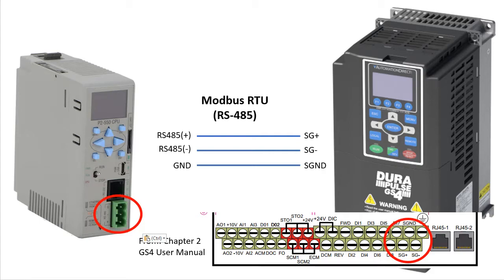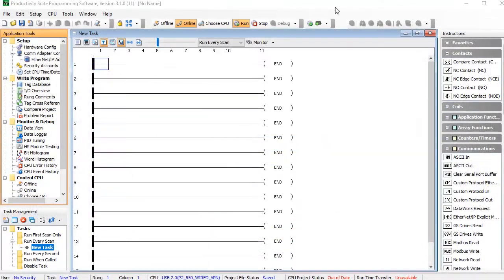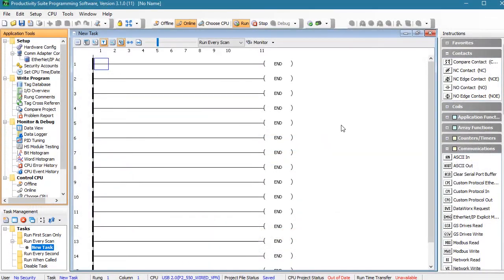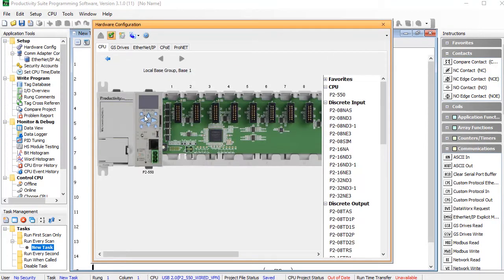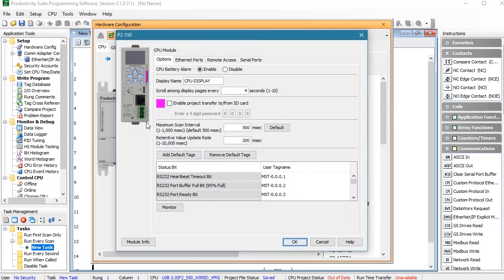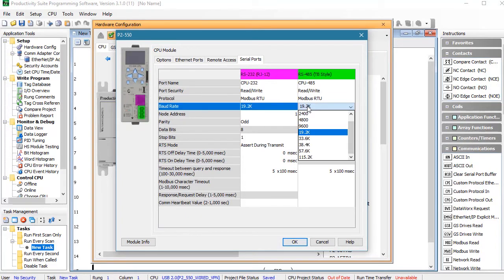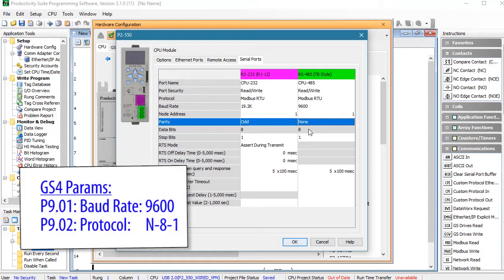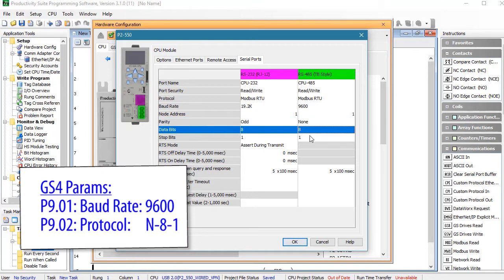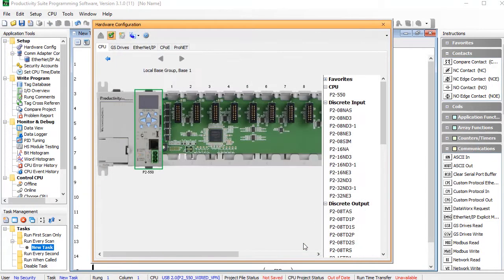I've already configured the drive for Modbus RTU using this video, so all we have to do is configure the Productivity Series controller. I've already connected to the Productivity PLC, so I'll open the hardware configuration, click on My PLC and double click on the CPU. On the serial port tab, we need to make sure that the RS485 port protocol matches our RS485 network. The GS drive's defaults are this, so I'll set the CPU to match that for this demo. The rest of this is fine, so I'll hit OK.